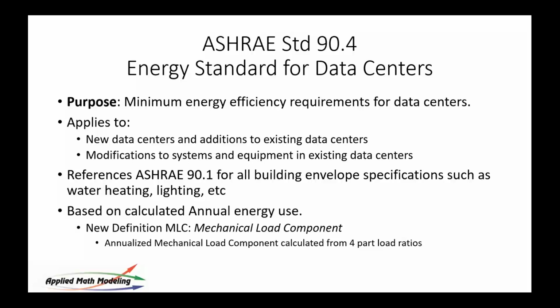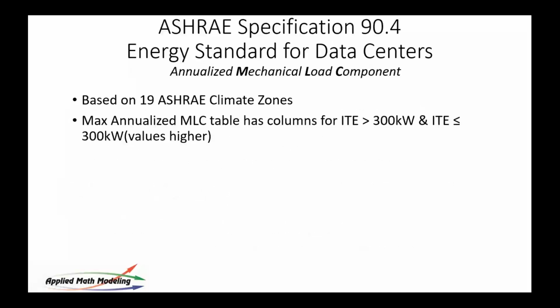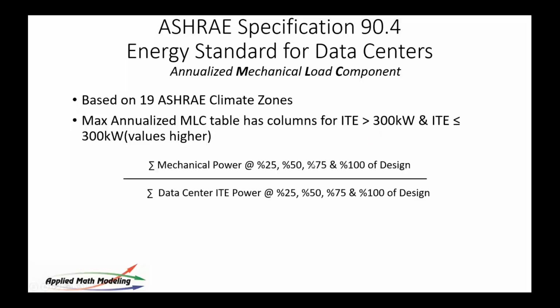And it's based on annual use. And there's a new definition in 90.4, which is mechanical load component. It's an annualized component calculated, and most recently, in the most recent spec, in 4 sections, based on 19 climate zones. And it also has specific ITE criteria as well. That's the IT side. And they use 4 points. It's mechanical power divided by IT power, effectively, at 4 different points.